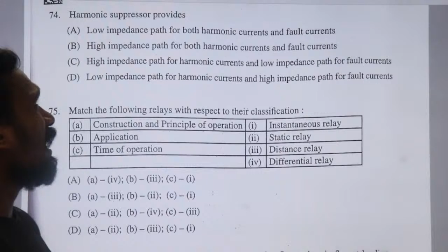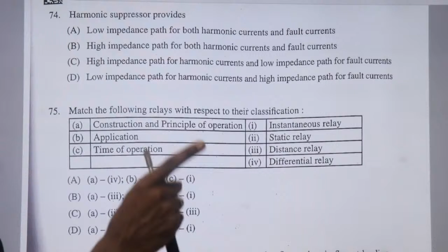Harmonic suppressors provide what, sir? They provide a low impedance path for harmonic currents and fault currents. Fault currents, okay, but what about the impedance? Is it high impedance path for both? No, that's not correct, option B is not correct. It should be high impedance path for harmonic currents and low impedance path for fault current. Harmonic suppressors are generally used to provide a low impedance path for fault current and high impedance path for harmonic current, such as third harmonics.